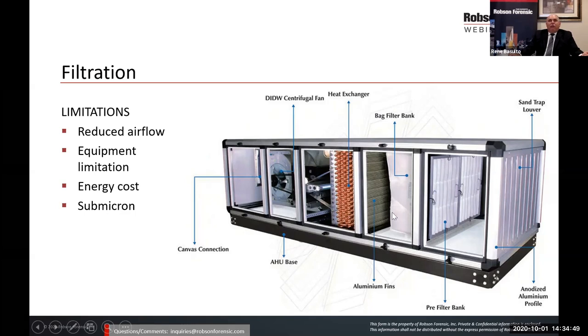It'll have a bag filter section right after it. Bag filters are very high efficiency type filters. Again, how filters work is they work on surface area and how to impact the most amount of surface area of the filter with the air. So the bag filters extend that surface area and they strain out the particulates in the air. But again, that offers a lot of resistance to the airflow.